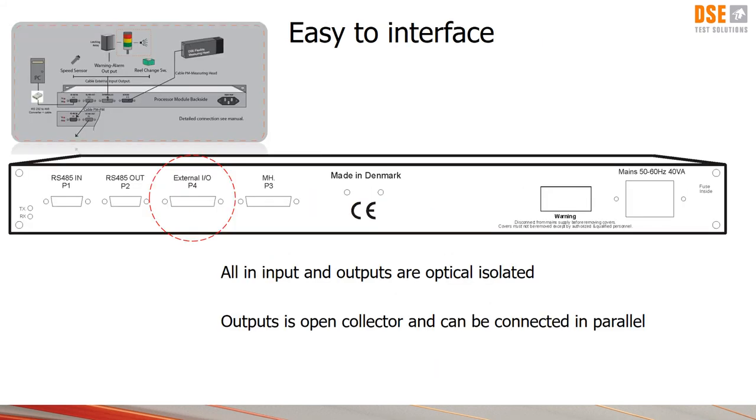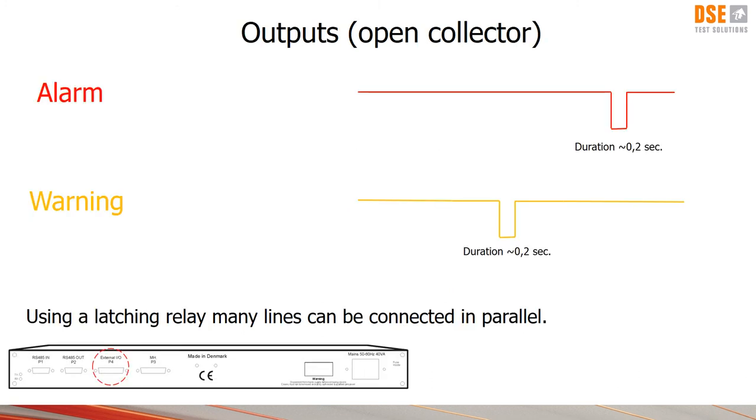Finally I would like to tell a bit about the in and output signals. Communication between the processor module and the PC is handled by USB or RS232 to RS485. And all modules can be connected in data chain and the PC can handle up to 99 processor modules. All in and outputs are optical and isolated. The outputs use open collector which makes it possible to connect them in parallel. The alarm and warning signal is changing status for around 200 milliseconds and by using a latching relay the alarm and warning stays until it's being reset by the operator.